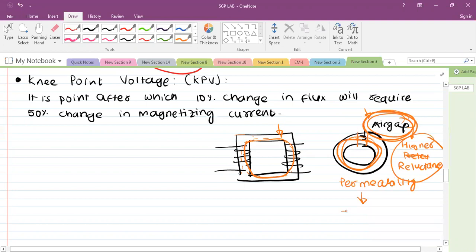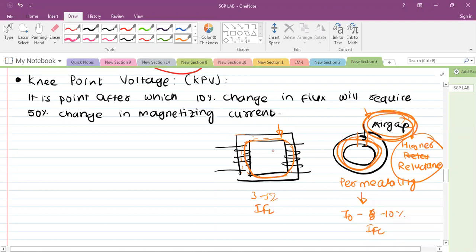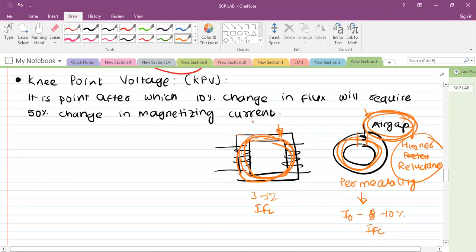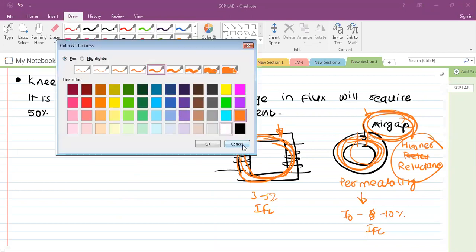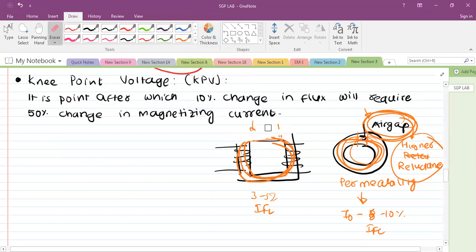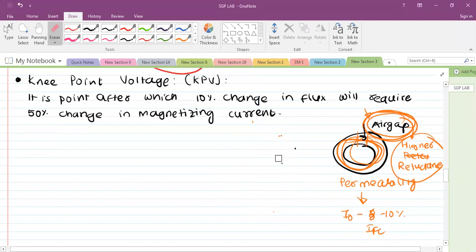So generally the no load current of an induction motor is 6 to 10, or 8 to 10%, of rated current, whereas for a transformer it is only 3 to 5%. Understand, the basic difference is the medium in which the flux is set up: here through the core, here through the air gap. Understand why the induction motor requires more no load current than the transformer to set up the same flux. Clear?